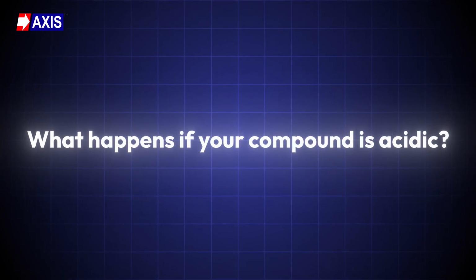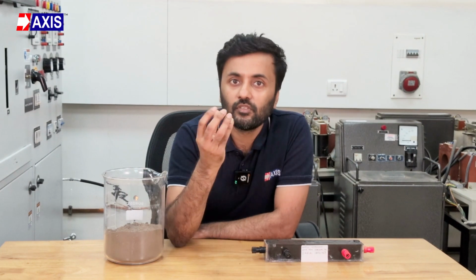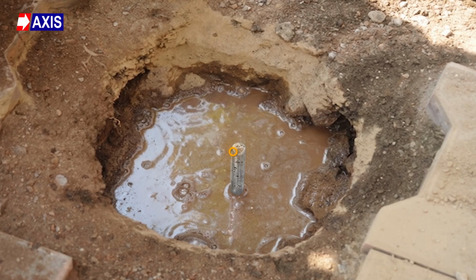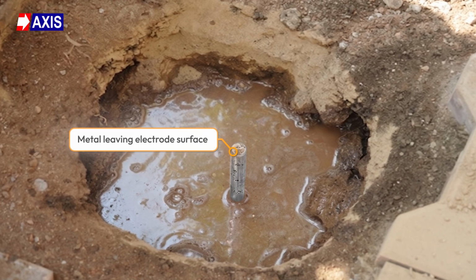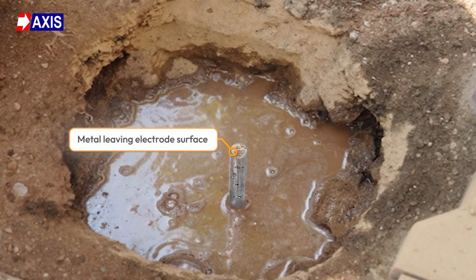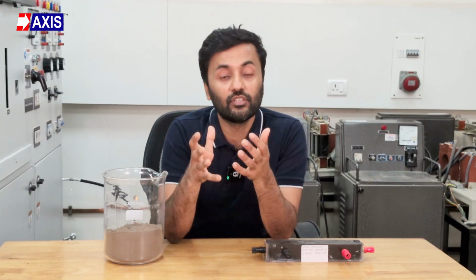But what will happen if your compound is too acidic? When such a compound surrounds your copper or galvanized iron electrode, it creates an acidic environment around the metal. This matters because the compound is not sitting dry around the electrode. As you know, it mixes with the moisture and forms an electrolyte solution. In acidic conditions, this electrolyte solution starts electrochemical reactions on the electrode's surface. These reactions dissolve metal ions from the electrode into the surrounding compound. In simple words, the metal slowly leaves the electrode's surface, and over time, this creates corrosion and it damages the electrode surface and reduces the service life of your earthing system.